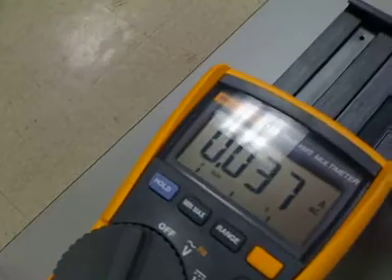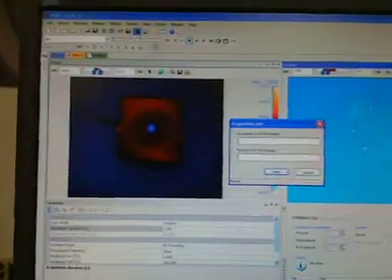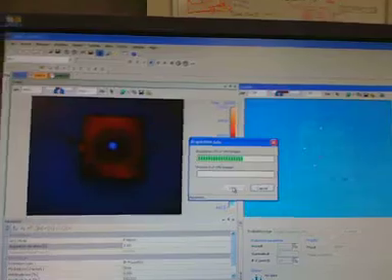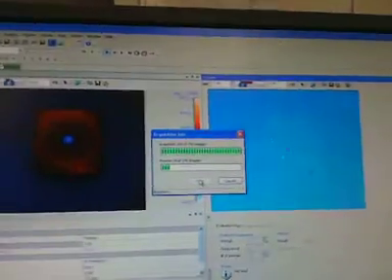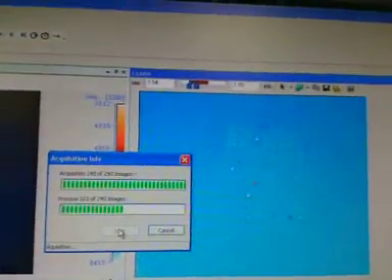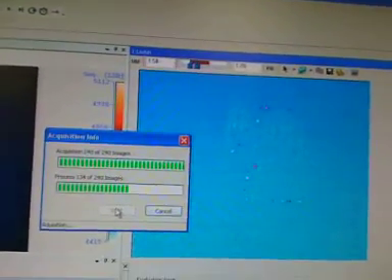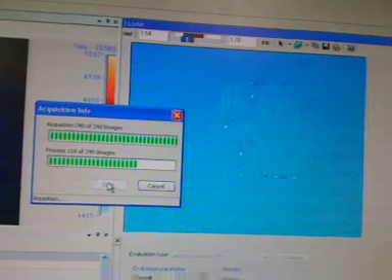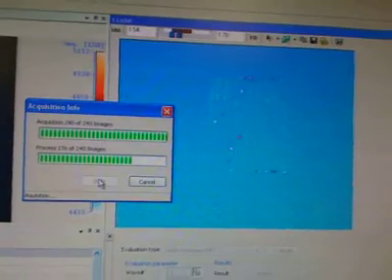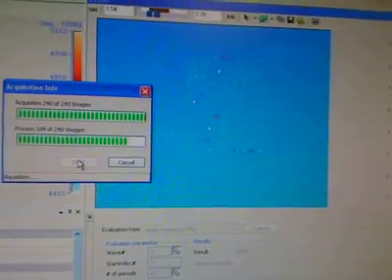So what I'm going to do now is I'm going to turn on the excitation source. And now I'm going to bump it up to 140. So that's 140 milliamps. And then we're going to do the measurement again and see if it makes a difference in our resulting image. And I'm expecting that it will. So depending on the material, it takes some playing around with. This particular solar cell is embedded in a piece of glass. So the settings for it are slightly different than for a bare thin film that you don't have to compensate for the heat coming through the glass.